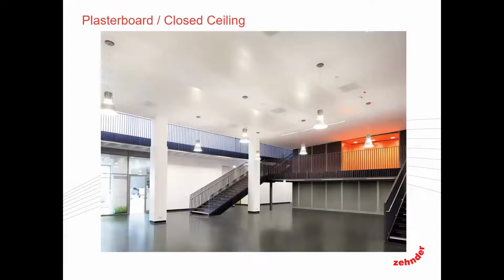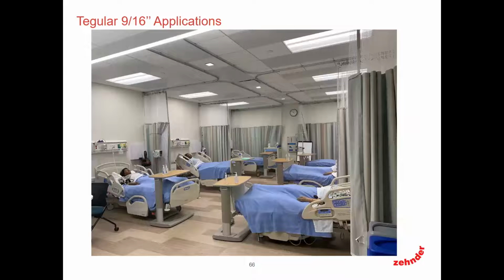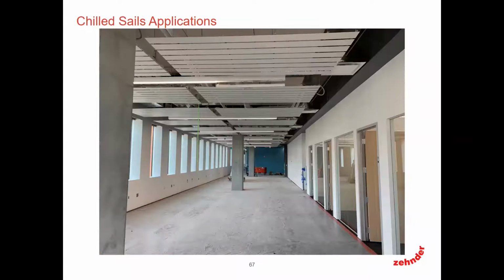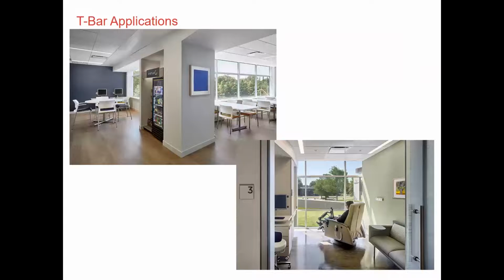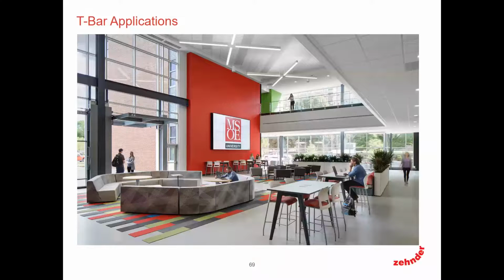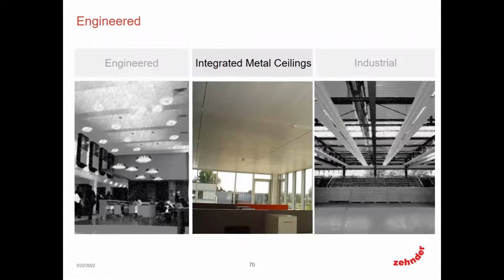Gypsum and plasterboard, closed ceiling applications. These panels come with torsion springs and a slot, so all these panels in the hard lid are accessible and drop down, so you can always get back into the plenum space. Tegular edges, again, whether it's 9/16 or lay-in, this was a teaching hospital. Molding manufacturers will integrate into any ceiling type with any different type of edge. Chilled sails, these are the extruded sails, extrusions, linear. These were 4x8s, copper tubes on the back. Again, these have a little bit more of a convective output than radiation, but again, another option, just a different aesthetic. Healthcare facilities, where we would see solid panels along the perimeter, and then higher bay, higher applications, 2-story lay-in panels up on the ceiling on the diagonal there. So again, I just wanted to give you a little bit of the gist of what these systems can look like.